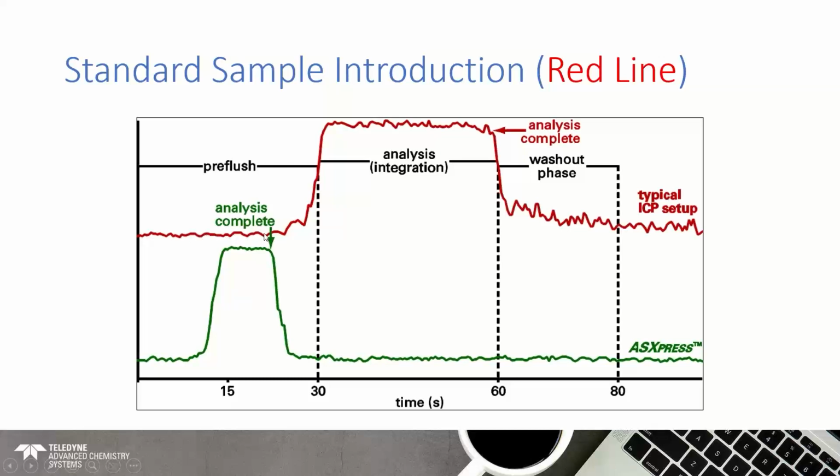the period that we're pulling the sample through the tubing via the peristaltic pump, and then all of a sudden it gets to the nebulizer and hits the plasma, and that sample signal starts rising, and then we get to our measurement stage. So let's say, for the sake of argument here, after 30 seconds, we're in a position to measure.